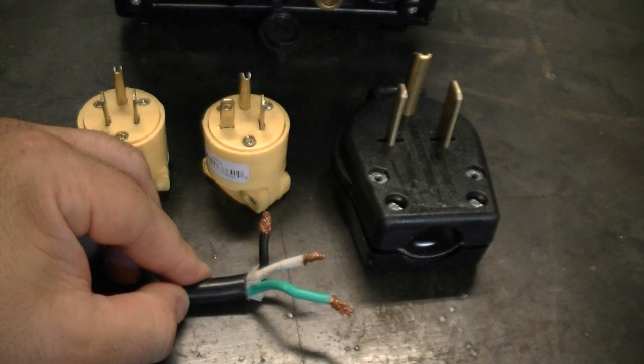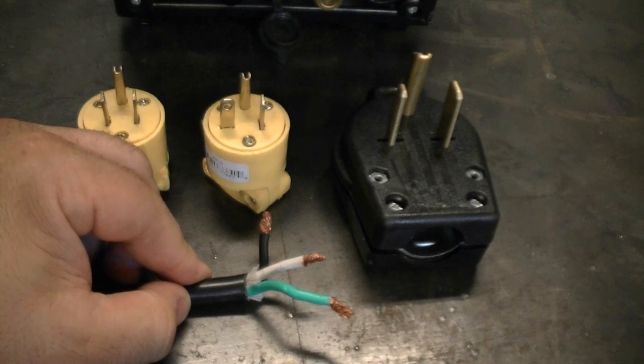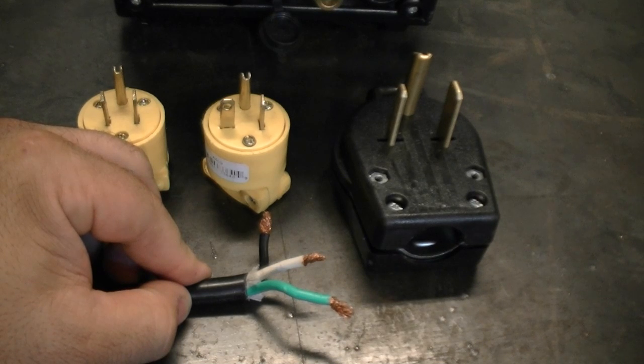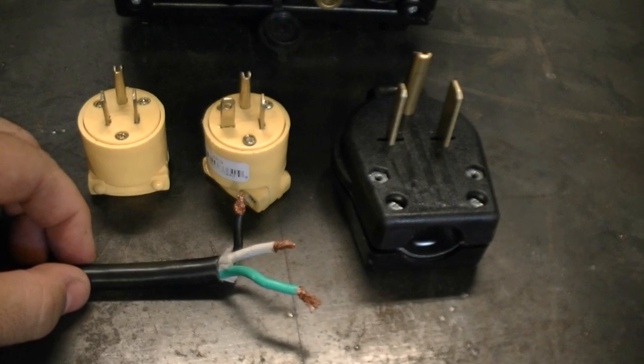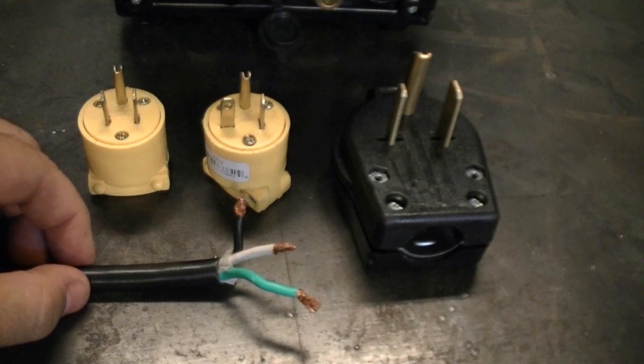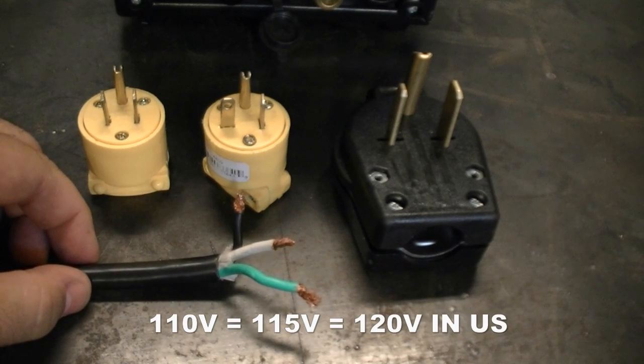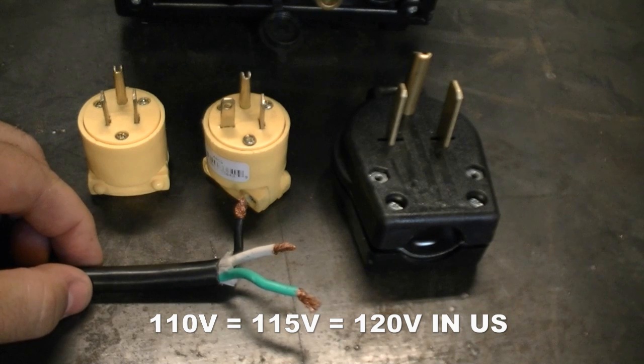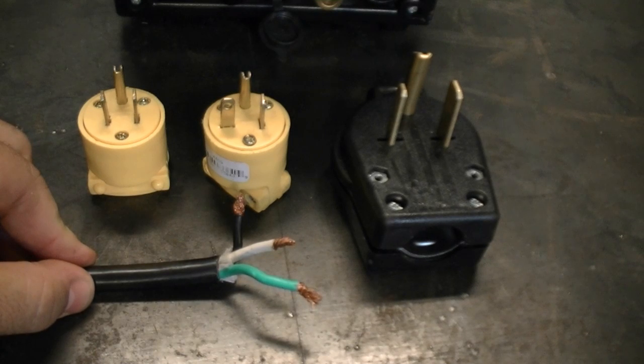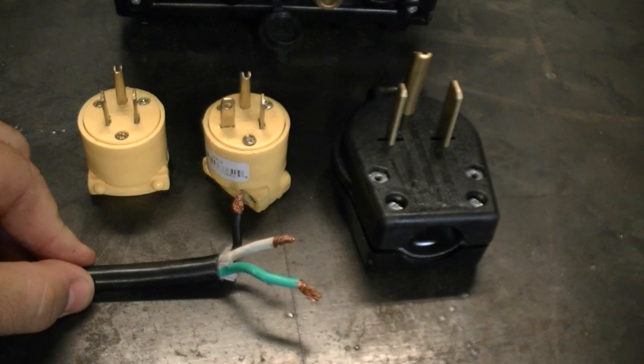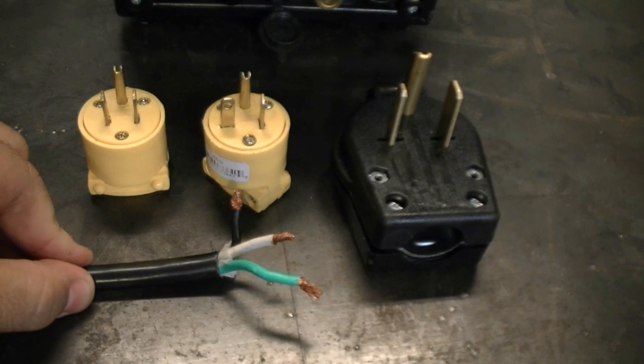In part one of the Power Ultra 205P video, we talked about the fact that these units are dual voltage. That means they'll run on 120 or 240 volts. To accomplish this though, you'll have to be able to change your plug out. With that said, sometimes for the low voltage operation, you'll see the voltage referred to as 110, maybe even 115, or as I said, 120. Now all these mean the same thing. Your actual line voltage could run up to 125, 127 volts, and down as low as a little under 110, depending on your actual local voltage supply.